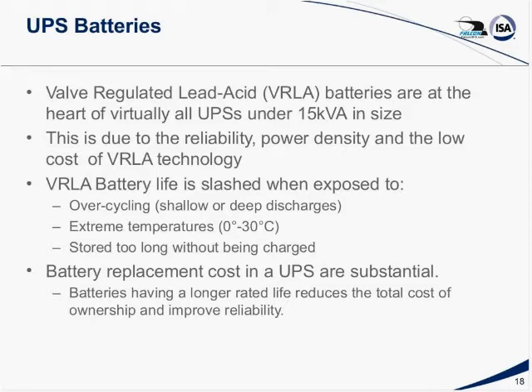Okay. In UPSs under 15 kVA, the battery that's used more than anything else is called a valve-regulated sealed lead-acid battery, or VRLA. It's the heart of the UPS. Lead-acid technology is used as opposed to the new lithium technologies and other battery technologies right now, primarily because of cost. And also it has a reasonable power density. However, the lead-acid battery has, as with most batteries, a couple of Achilles heels, and one is overcycling.